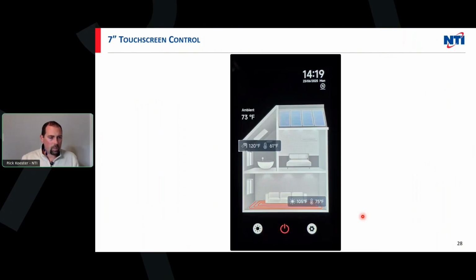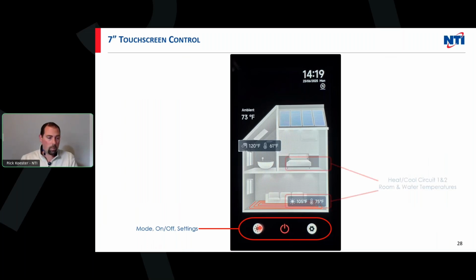Just looking at the screen, we're going to go over this a little bit more when we get into the programming and setup of this machine, but just to look at the display itself, it's very easy to interact with. I like to compare this to the cell phone you have. It's so simple to navigate and very fast reacting. What you're seeing on the screen here is our mode on/off and our settings button. If the system is programmed properly and we activate the system, you will see a blue light here instead of a red. If that is red, that just means there's power there, but the system will not run. So we can disable the system from here. The components are still going to have power to them, but we can shut down everything right from the touchscreen. We can select our modes, so depending on how we program the machine, we'll be able to turn on manually to heating, cooling, domestic hot water, however we have it programmed, or we can do automatic, which we'll talk about in a few minutes as well.